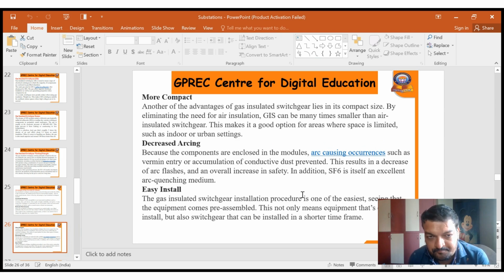Next, decreased risk of arc flashes, because the components are enclosed in modules, which prevents the entry or accumulation of conductive dust. So such occurrences are less likely because of this enclosed module. This results in a decrease of arc flashes and an overall increase in safety. In addition, SF6 is itself an excellent arc quenching medium. Because of its high dielectric property, it itself reduces the arc flashes, and by reducing the arc flashes it acts as an excellent arc quenching medium. That is the main advantage of SF6 gas.